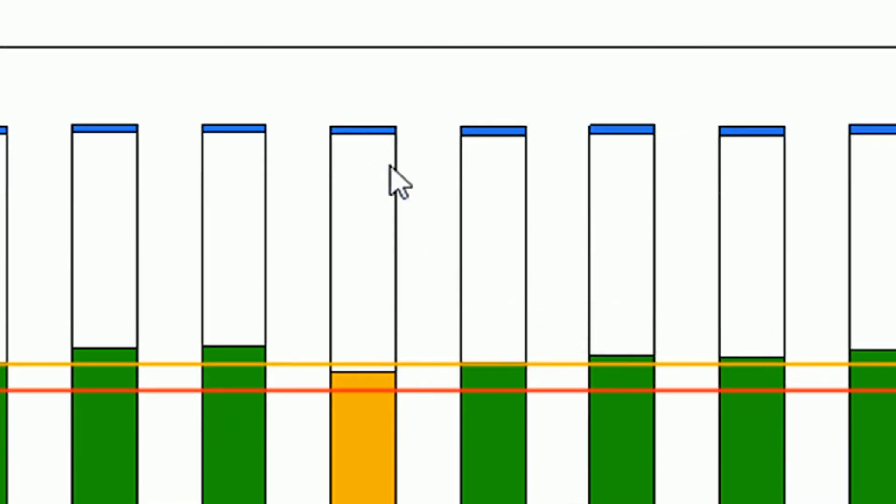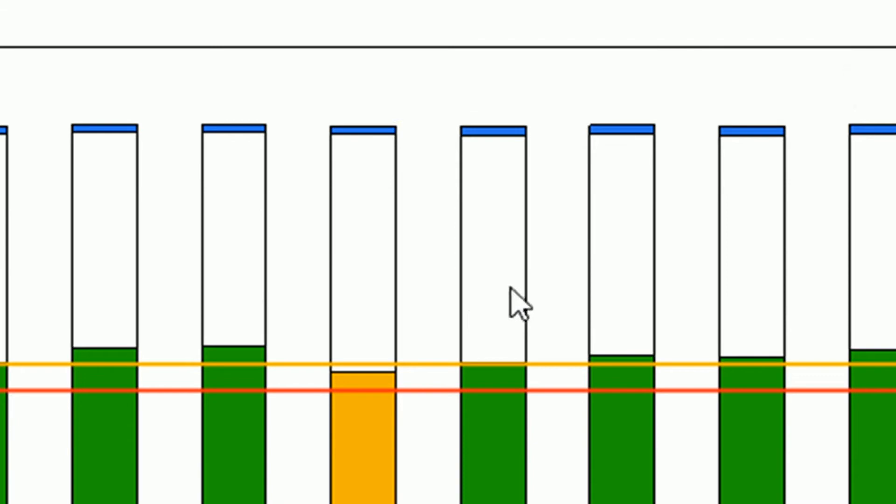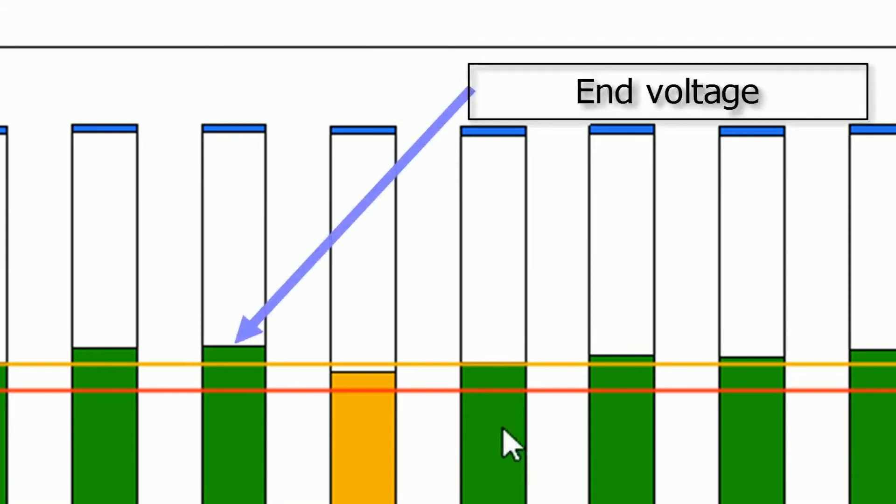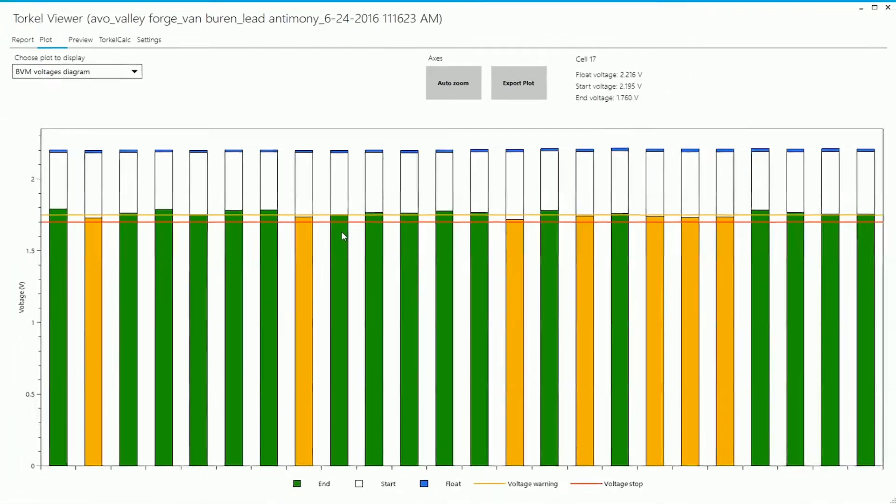The upper end of the blue section corresponds to the float voltage for that particular cell. The upper end of the green section corresponds to the end voltage. You can see two horizontal lines there - those are the warning and the stop limits set for individual cell voltages.